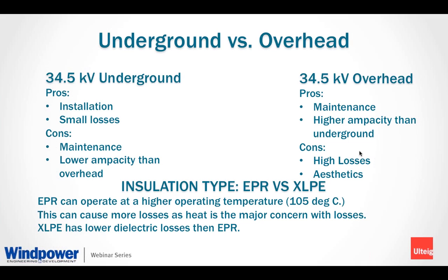The differences between these two materials is EPR has been around a lot longer. This type of insulation tends to have a higher loss, but the advantage of this type of insulation is you can run the cable to a hotter temperature, 105 degrees C, versus XLPE tends to be 90 degrees C for its maximum operating temperature. The XLPE type insulation has an extremely decreased dielectric loss compared to the EPR. So using an XLPE insulation can help your losses over time.